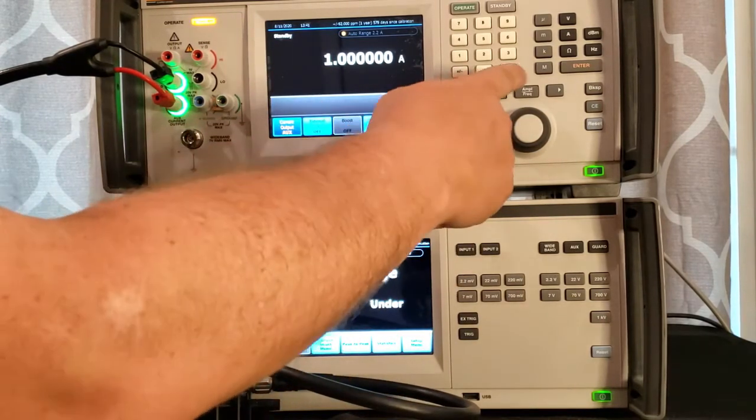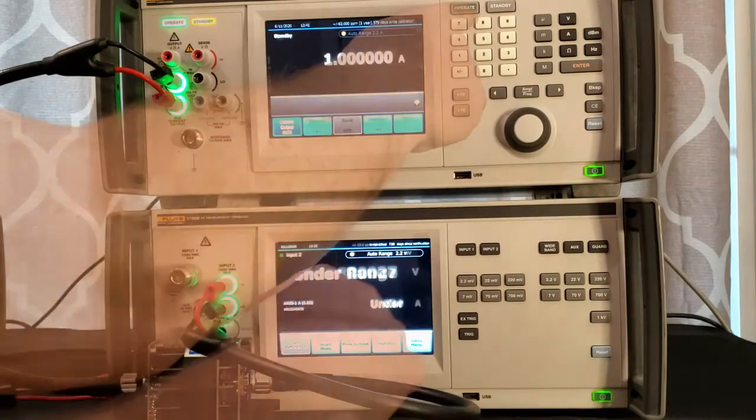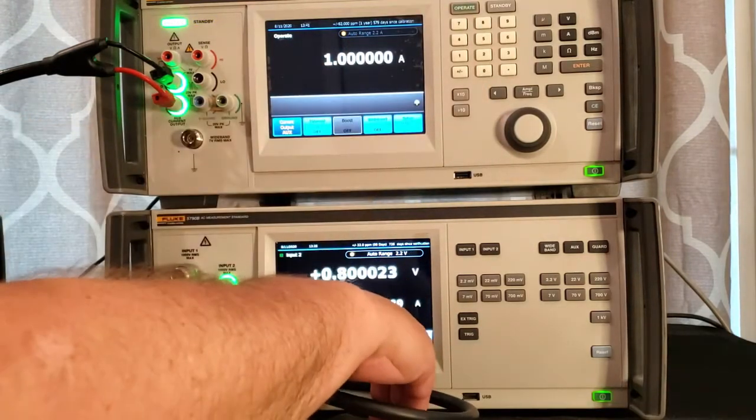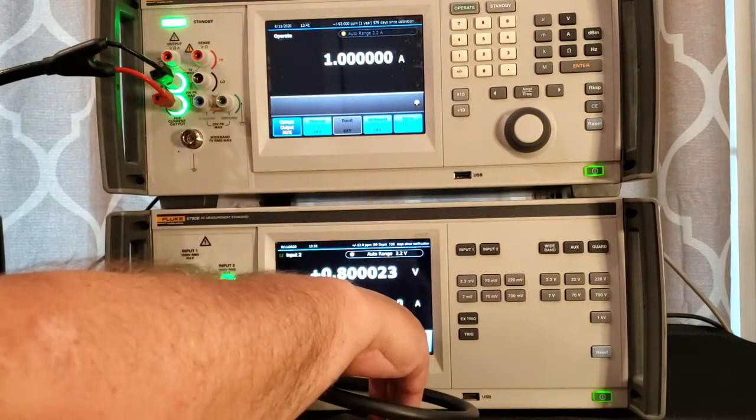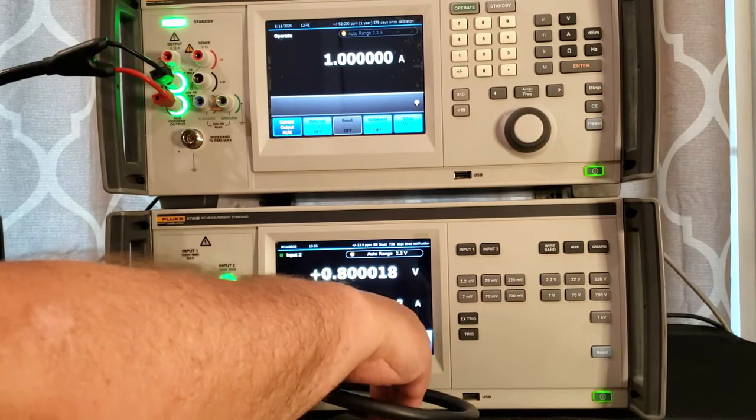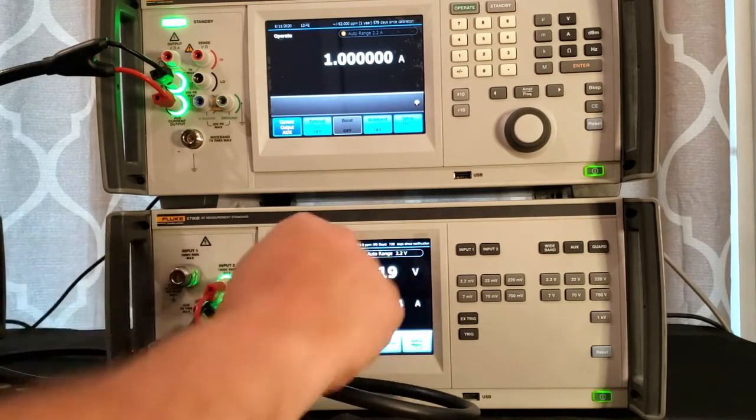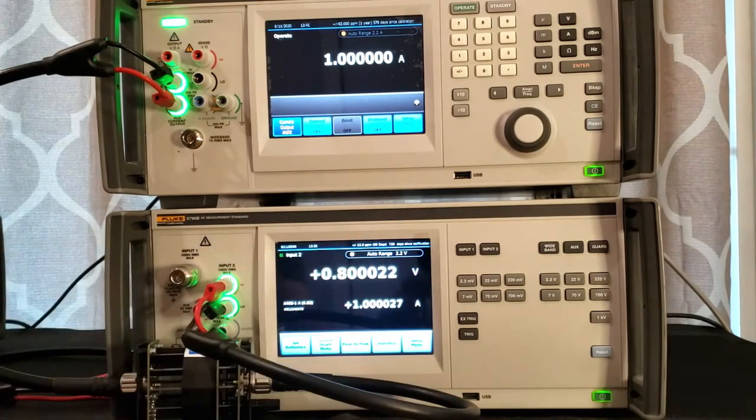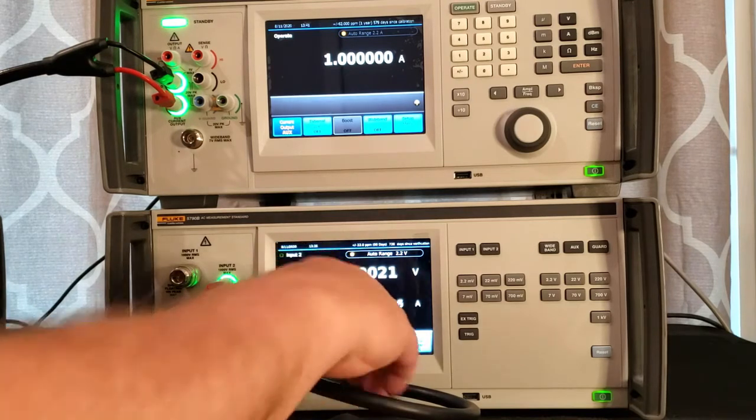I've got one amp set up on my 5730A and now I've got my corrected current output. This is the actual voltage. 800 millivolts is being applied. This is the corrected output.